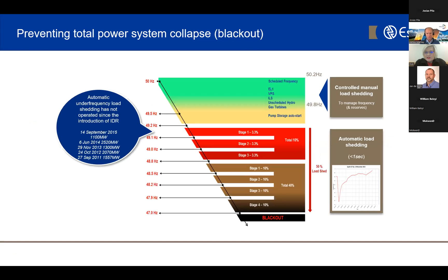We also have unscheduled demand reduction. This is when we have an incident on the network and we have to react within milliseconds. It's our under frequency protection scheme. As you can see, there are a number of stages of the under frequency scheme. If you concentrate on the red block, we have never gone beyond the first stage. So just to give you some comfort, we have more protection installed. This is hardwired into the network and it is well functioning and properly tested on a regular basis.